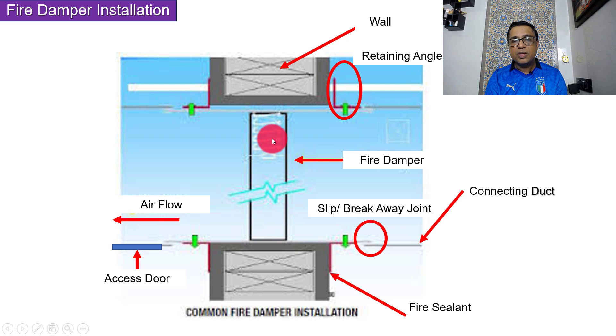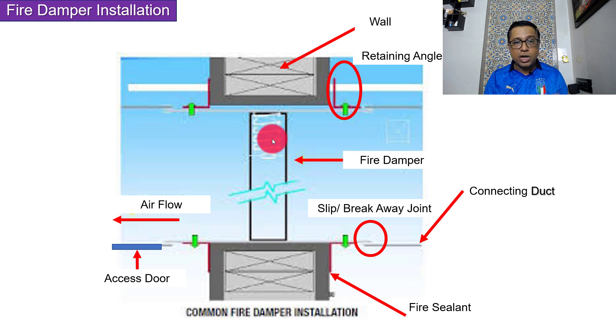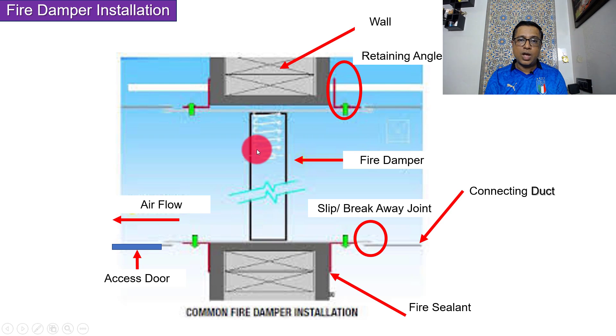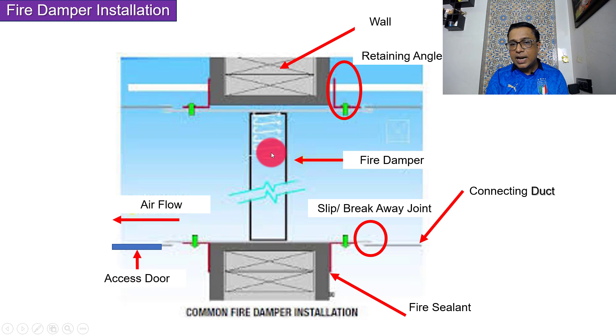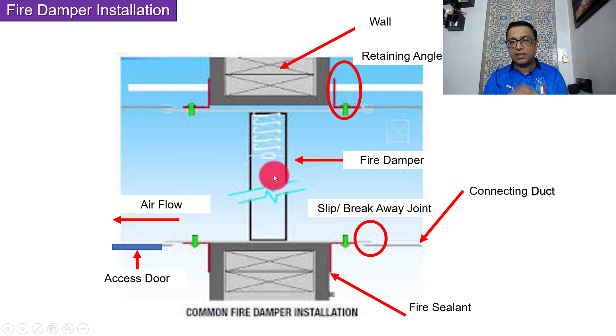With a fusible link fire damper, there are chances the fusible link might get damaged or may not work. In that case, the entire airflow might be affected. So you must have an access door — and if there is a ceiling, an access point in the ceiling as well — so you can go in and service the fusible link.